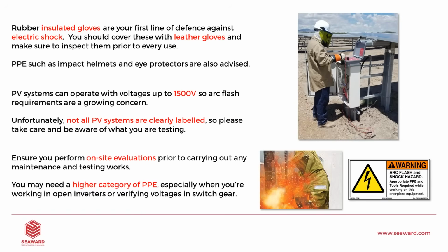So with regard to safety, we're facing, as I say, higher voltages, higher currents. So arc flash is a real serious concern. So we should always be prepared for the worst. We should wear rubber insulated gloves. They're our first line of defense. Cover those with leather gloves. Wear the correct PPE. We need eye protectors. We need impact helmets. We should have our arc flash rated jeans and jackets.